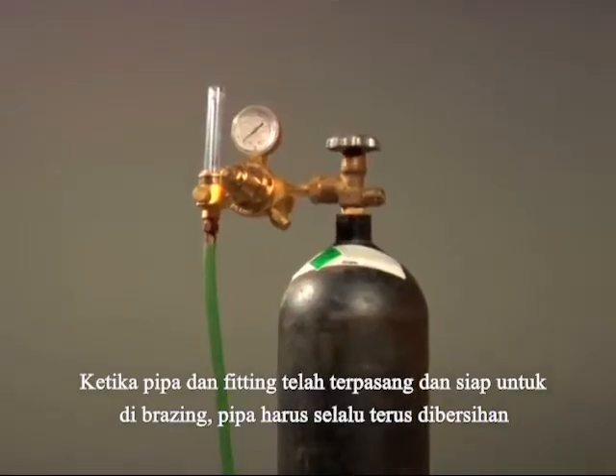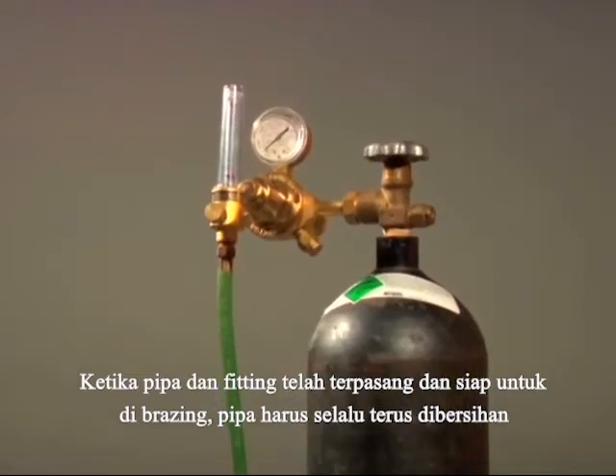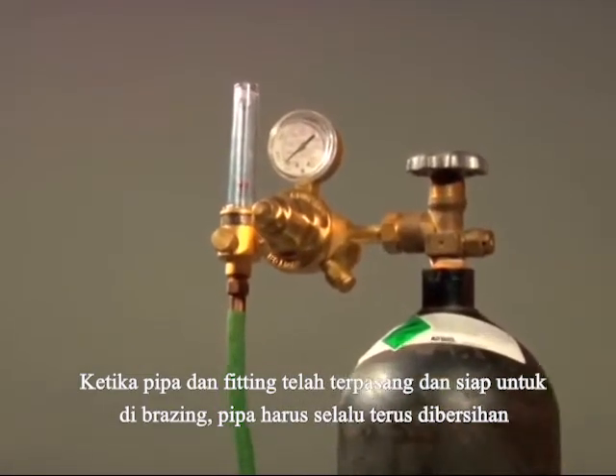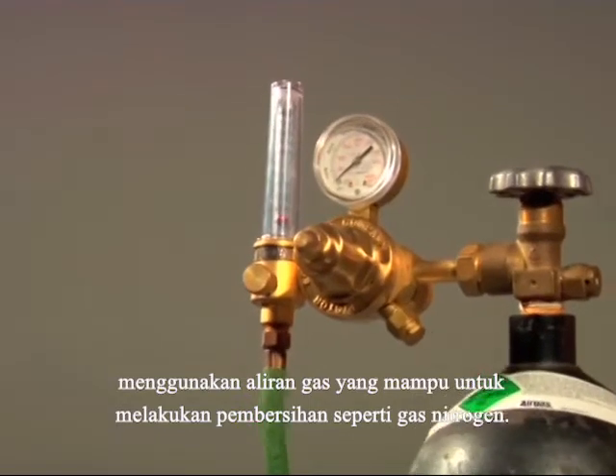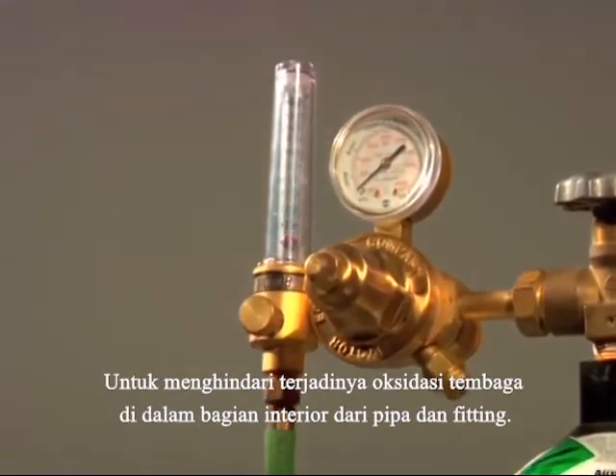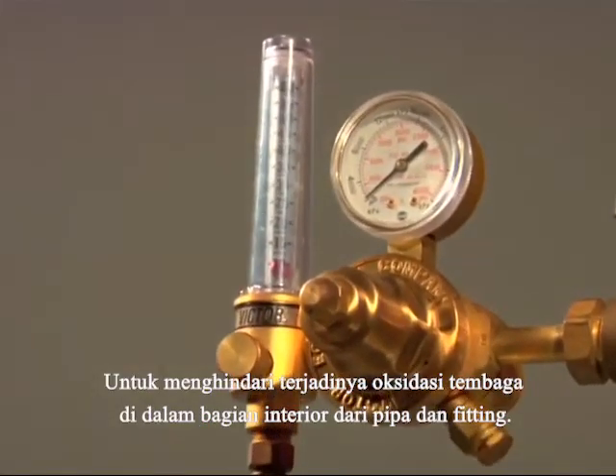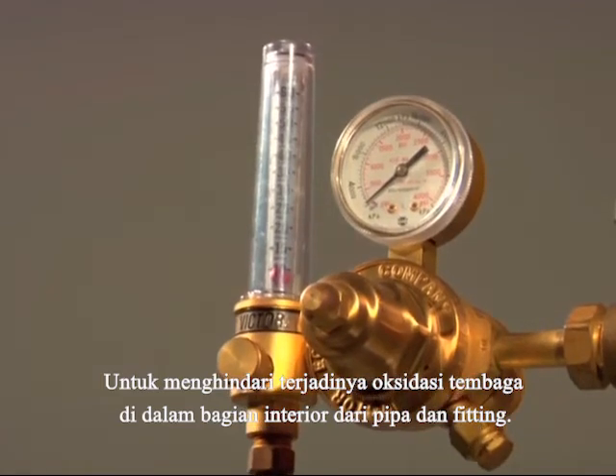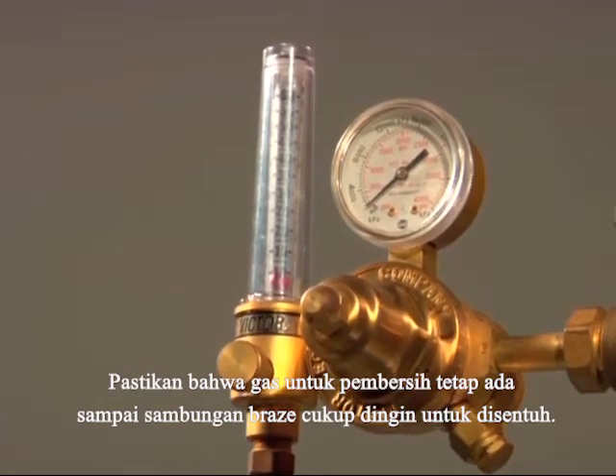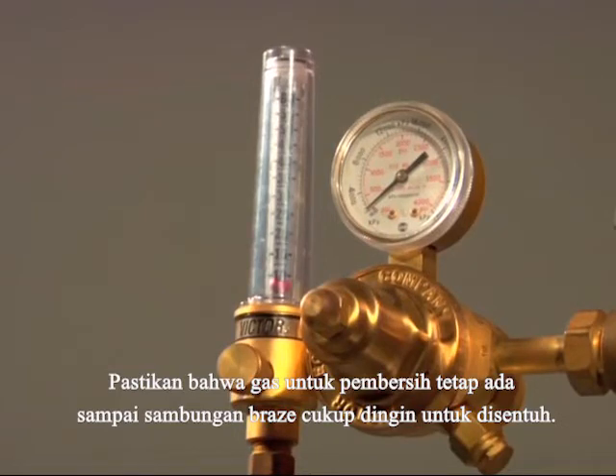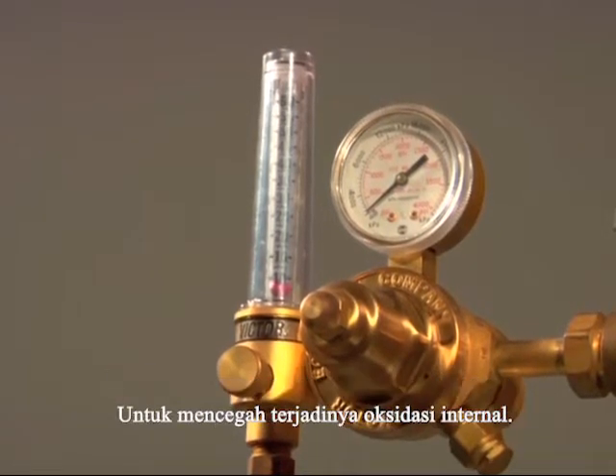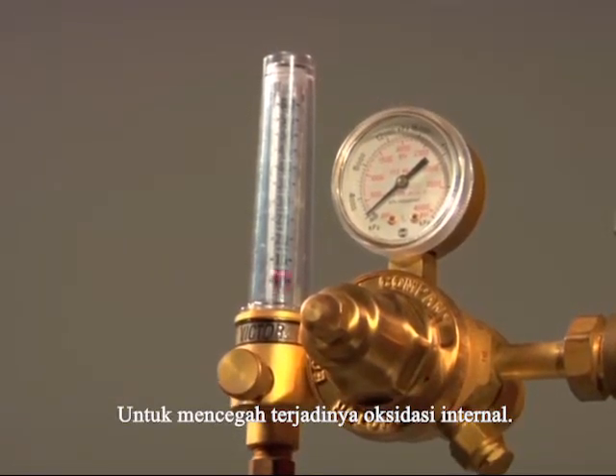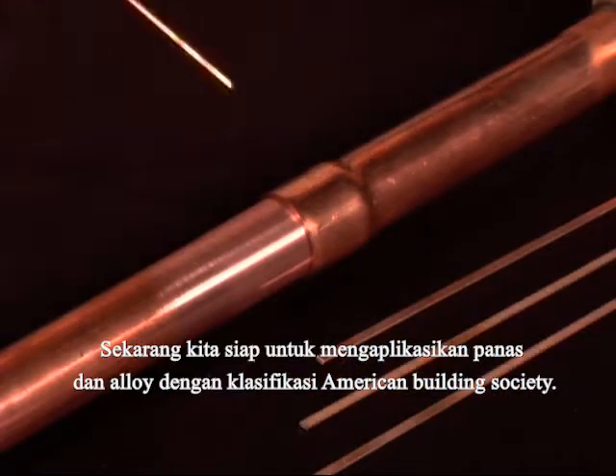Once the tube and fittings are assembled and ready for brazing, the piping must be continuously purged with an approved purge gas like nitrogen to prevent the development of copper oxides on the interior of the tube and the fitting. Be sure to keep the purge gas on until the completed brazed joints are cool to the touch to prevent internal oxidation. Now we're ready to apply heat and alloy.